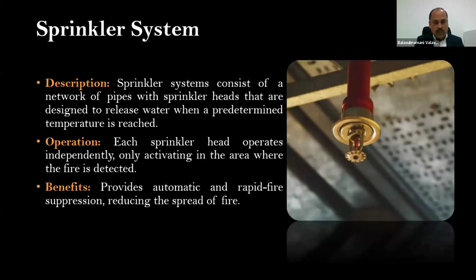What happens when there is a fire is that it will be detected, with respect to the temperature. For example, if it is an orange bulb, yellow bulb, or even green bulb, take the case of the green bulb: when the temperature reaches 93 degrees centigrade, the liquid inside the bulb expands and its pressure also increases. Temperature and pressure are proportional. When it reaches that temperature, the pressure increases and the bulb breaks. The moment the bulb breaks, it allows the water to spray on the entire surface, thereby putting off the fire.